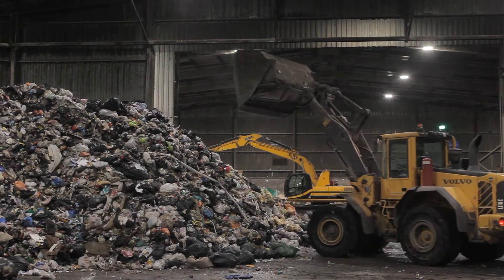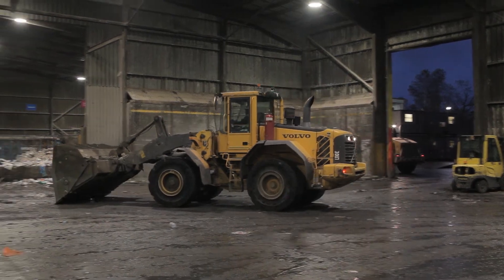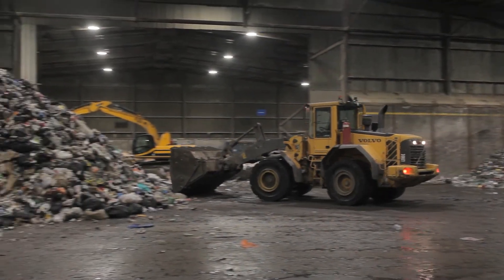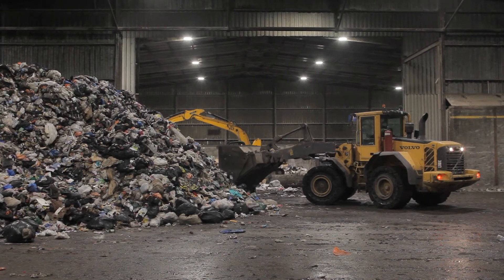From a health and safety point of view, these lights produce very low amounts of heat. With the previous lighting, there was the possibility of the bulbs exploding and hot shards raining down onto combustible material below, and thus causing a potential fire. It was quite a large hazard, but with these lights there is not that issue.